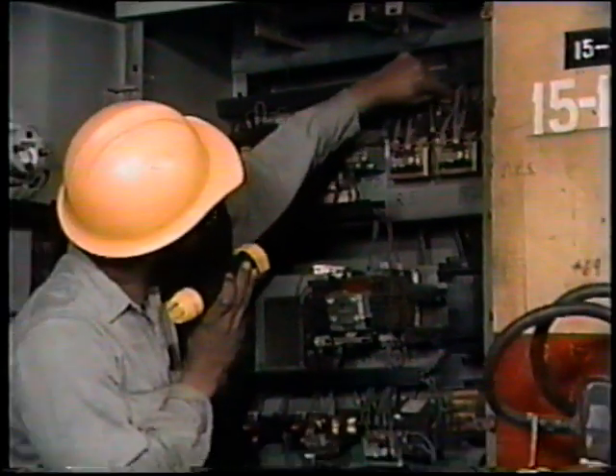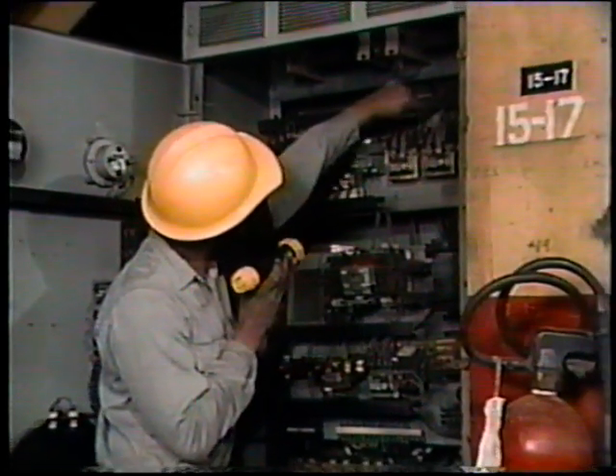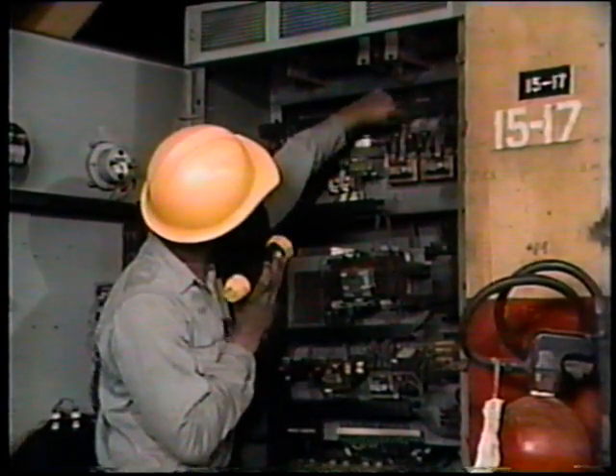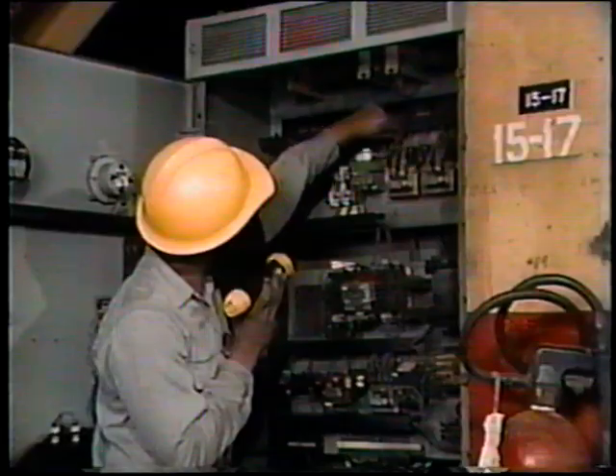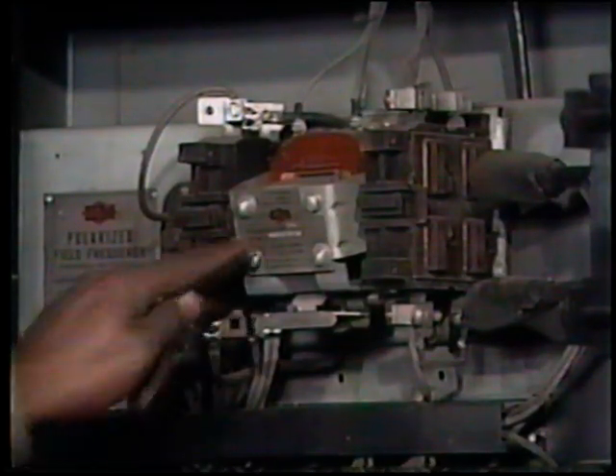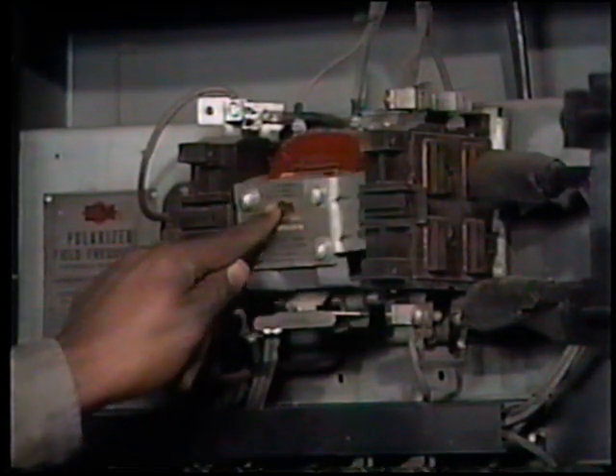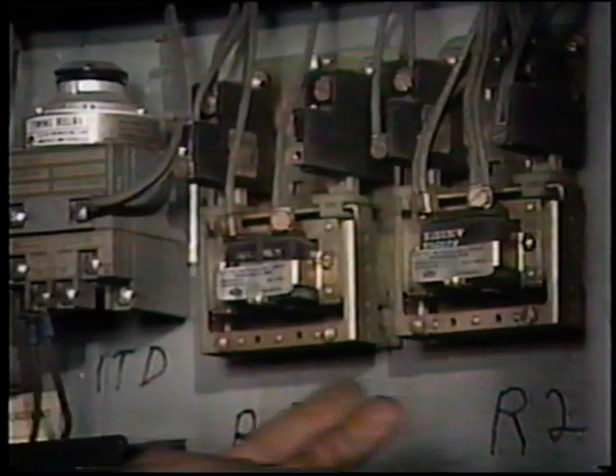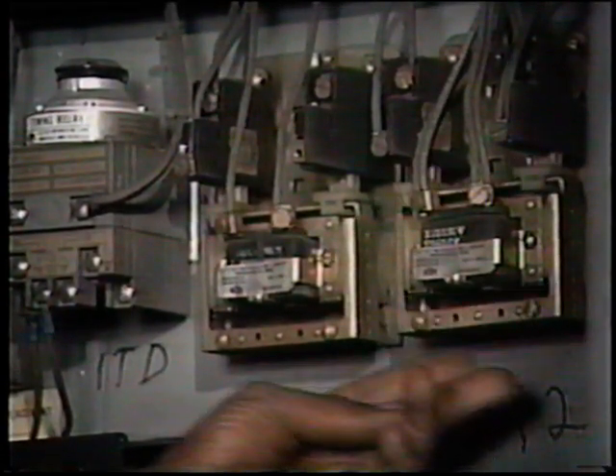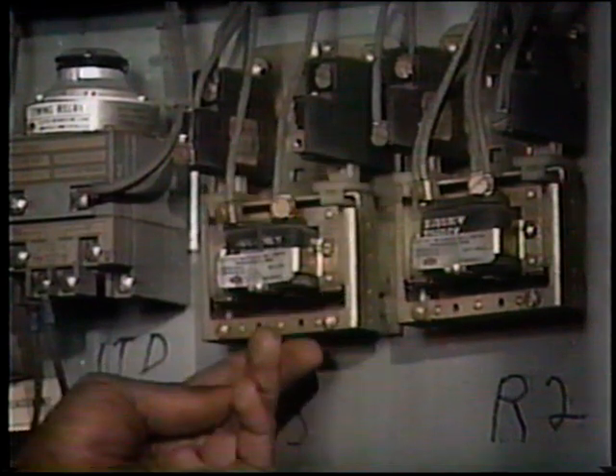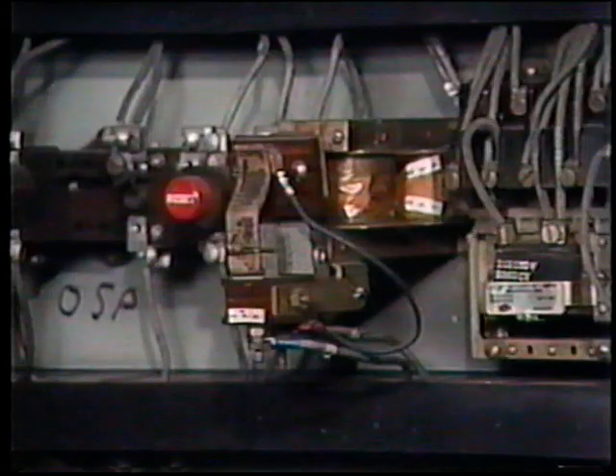Look for frayed or cracked insulation. Make sure all of the controller's connections are tight. Then check all controller relays. Manipulate each relay by hand and make sure they are operating properly. Check the surfaces of the contacts and make sure they are clean and making good contact.